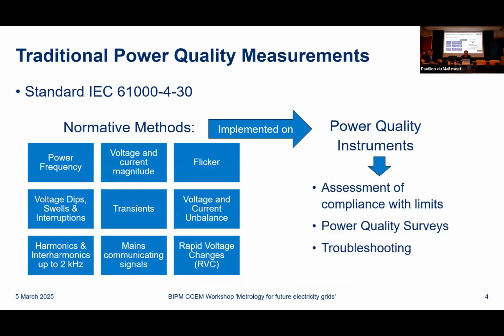Now, traditionally, or still today, really, you can go to the 61000-4-30 standards, and that will give you normative methods for a range of power quality phenomena, including the frequency itself, for example, harmonics are a very big topic, also voltage dips and swells. I won't mention all of them, but this is the set of power quality parameters where we've got normative methods, they're well-defined, everybody uses the same methods, everything's comparable, and then they're implemented by manufacturers on power quality instruments, and then they use them to check whether in their grids everything is compliant with the limits, and if there's a problem, they will try to understand where it comes from in order to rectify it.